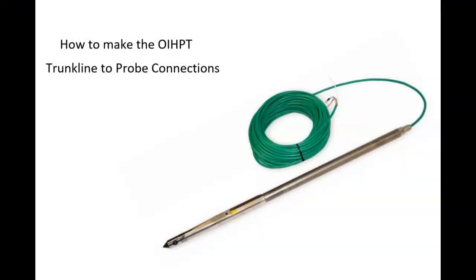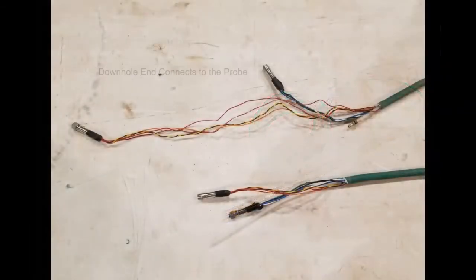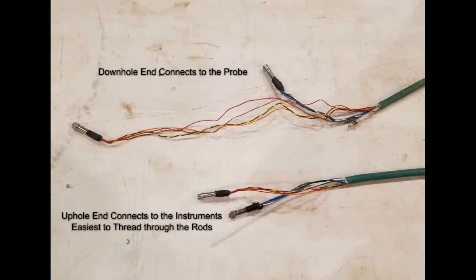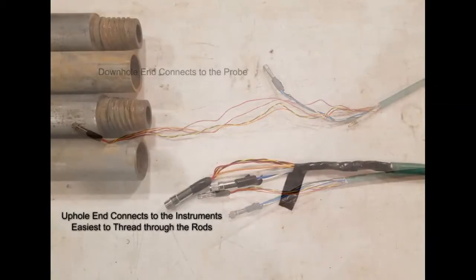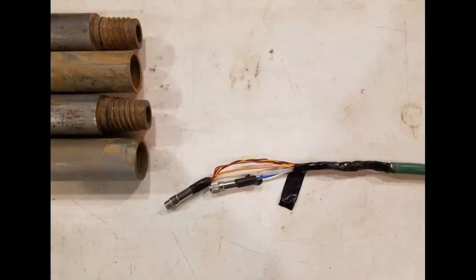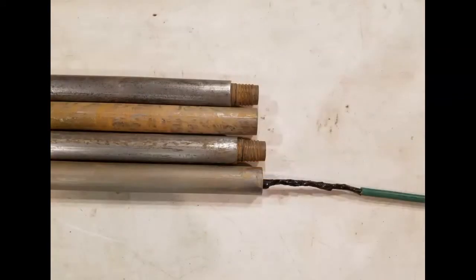In this video, we will demonstrate how to make the proper OI-HPT trunk line and probe connections. First, let's look at the two ends of the trunk line. The end with the varying wire lengths is the down hole or probe end of the cable. The end with the similar wire lengths is the up hole or instrument end. This is the end that's going to be easiest to tape up and thread through the probe rods.